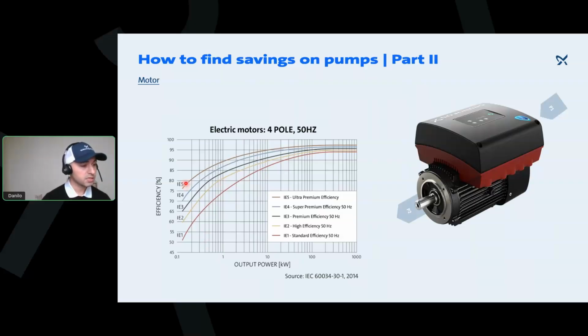While the IE5 motors are still somewhat on the flatter side, they keep their high efficiency. Another interesting thing is how these motors are constructed. The super premium efficiency motors usually have the little fan. Not that this one doesn't, it does, but because of how they operate, the turn down ratio for a regular motor is about 25 to 30%. So you cannot run them lower than that.